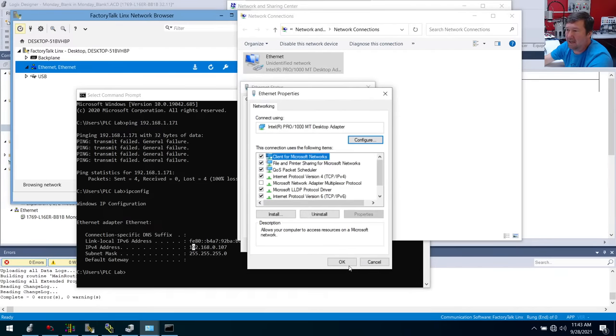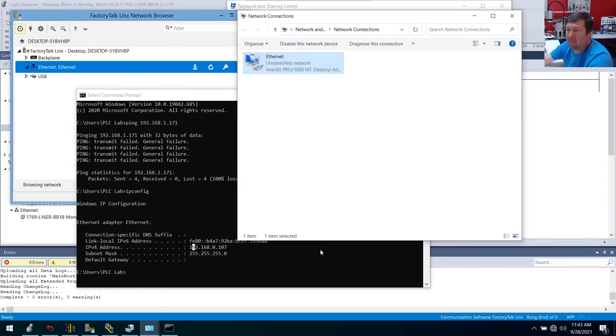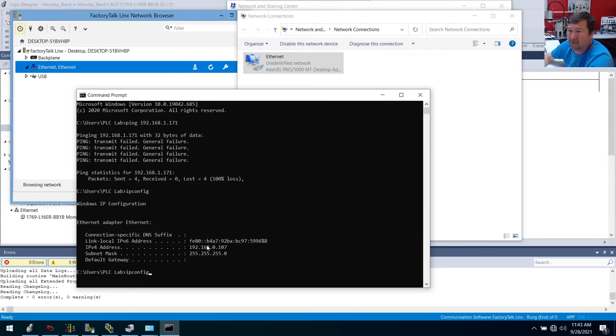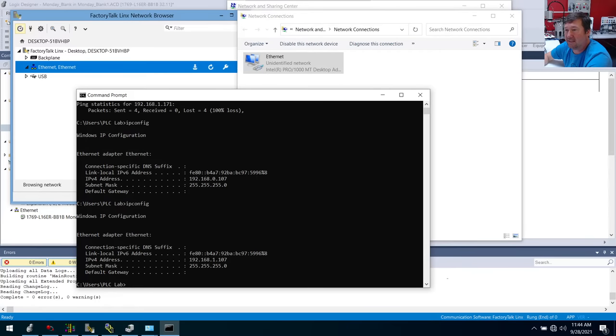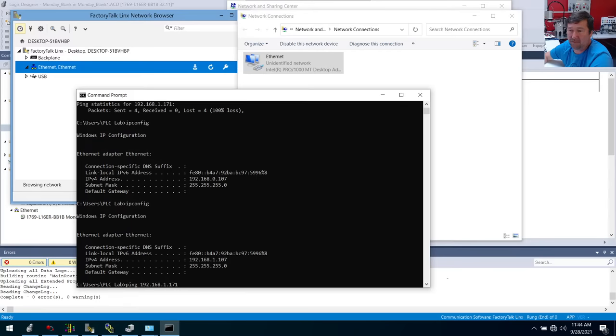You have to be really careful doing this, because if you happen to put an IP address in that is already used on a network, you can make devices cease to talk and can take systems down. Really, this is where you've got to document these IP addresses. Now, see, it says 192.168.1.107. And our IP we're going for was 1.171. If you hate typing, if you'll hit the up arrow, it'll give you your last command. And if you'll hit the up arrow again, it'll give you the command before that — you can scroll through the commands you've entered. And now we have a reply, mainly we're getting a reply from the IP address that we pinged. As long as we get that, then we're ready to communicate.